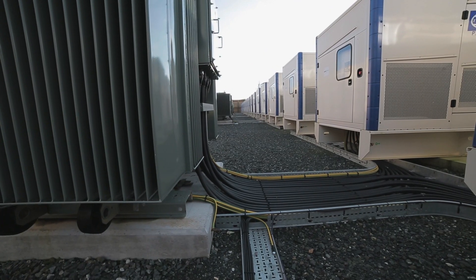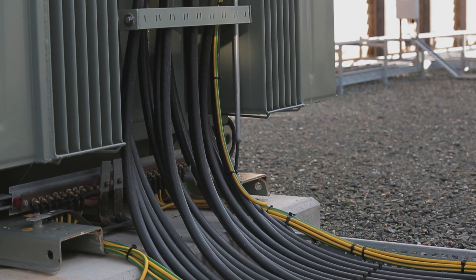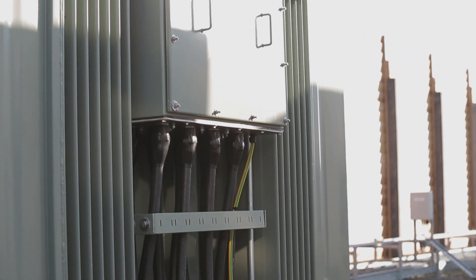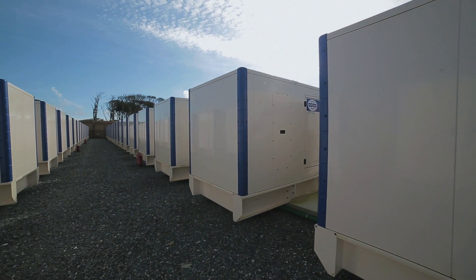When running under FFR, that really can be quite a challenge. There is just 30 seconds for the engines to get their start signal, start, synchronise, and run up to their full output power — something that we regularly achieve in something like 24 seconds.